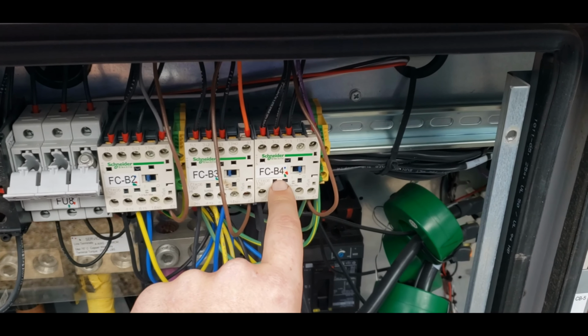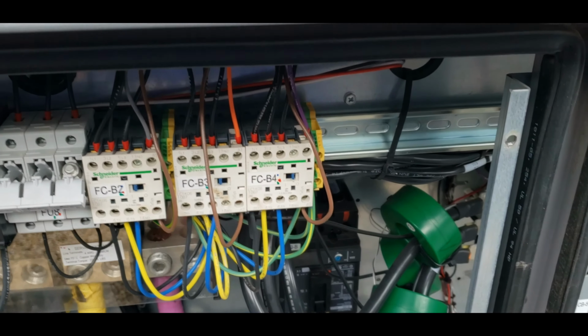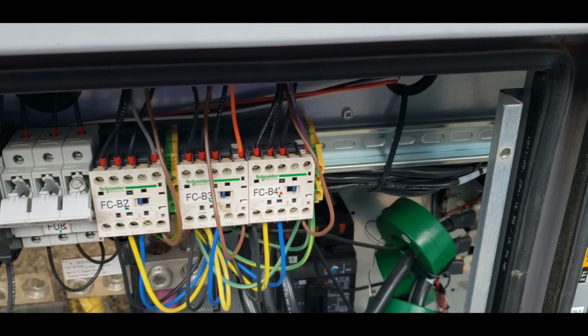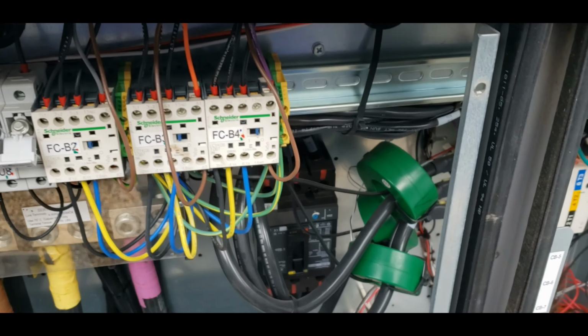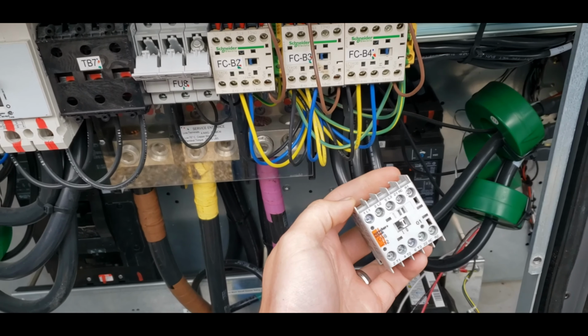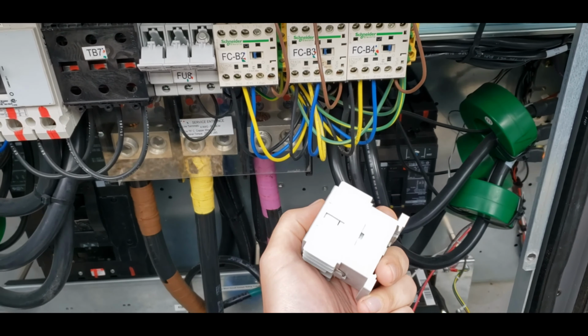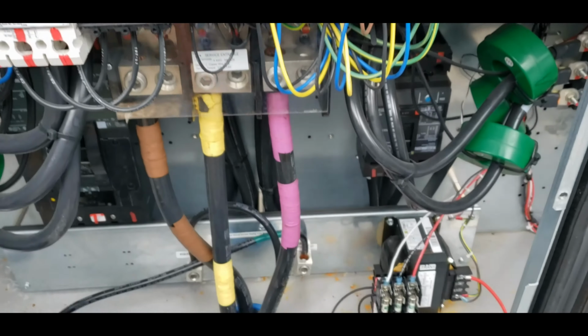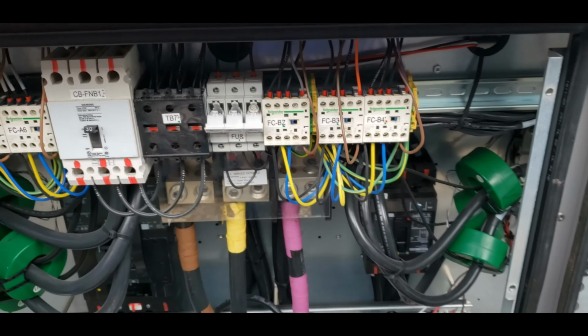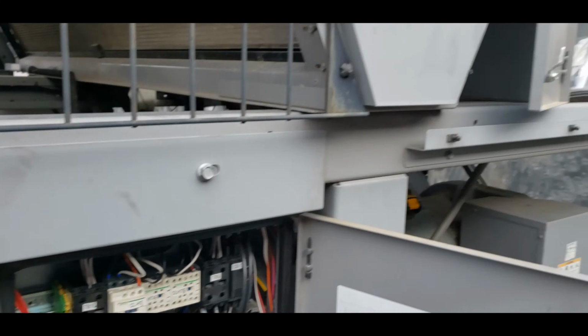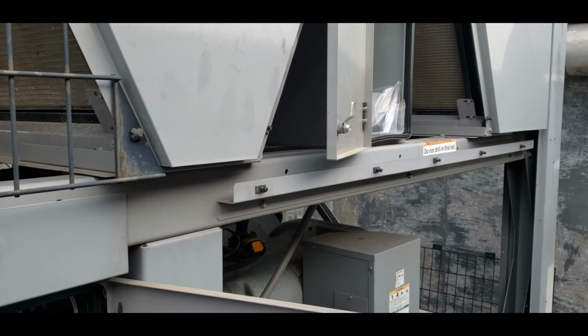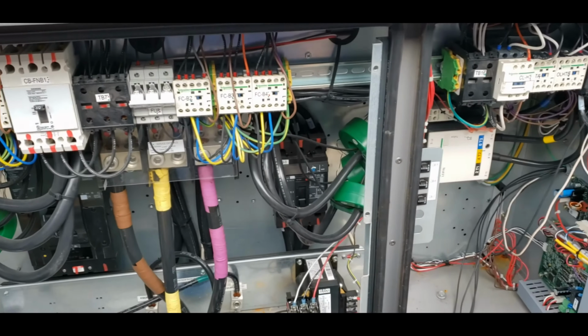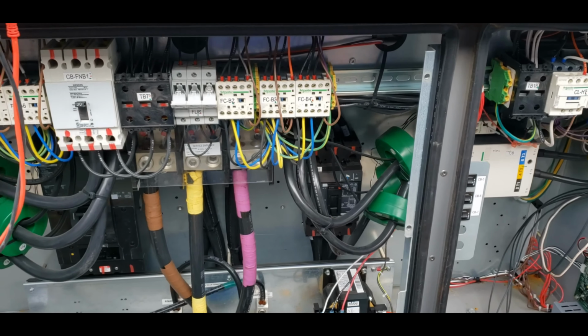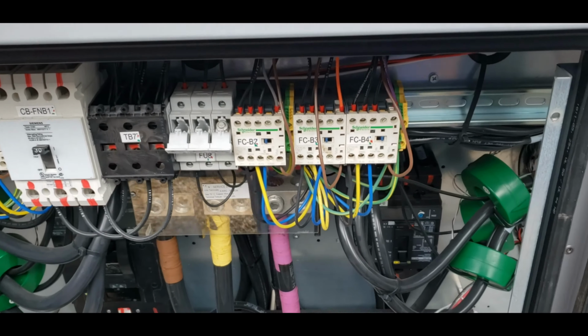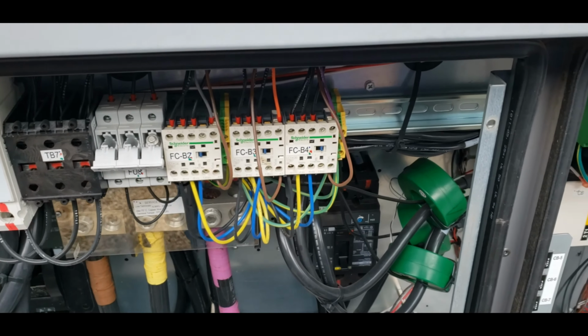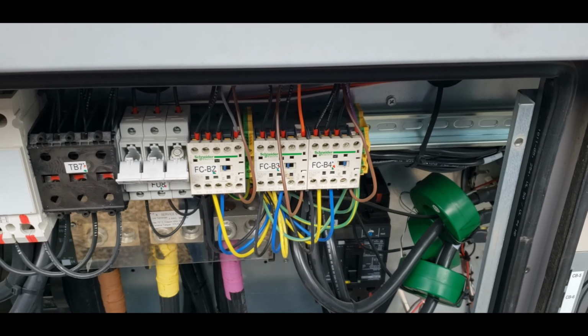This Carrier has a bad condenser fan contactor. It's got 24 volts in the coil, but it's not pulling in. So customer approved putting a new one in, so we'll get them switched out, get her back online. Funny thing is, that's actually the same circuit that they lost the condenser fan VFD on. So right now they've only got 2 circuits running on that, or 2 fans running on that circuit. So that'll really help that compressor out.